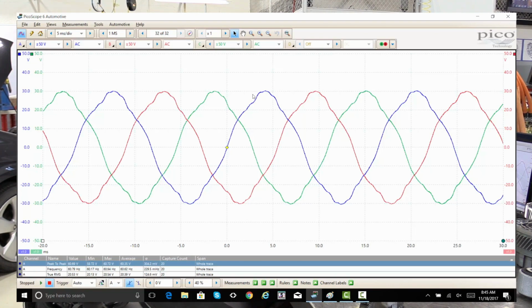Measure the phase difference between the waveforms of each phase. Each phase should be 120 degrees out of phase with the others. This can be observed as a 1/3 cycle shift on the oscilloscope display. The waveform should be sinusoidal. Deviation from the sinusoidal shape can indicate harmonic distortion or a fault.